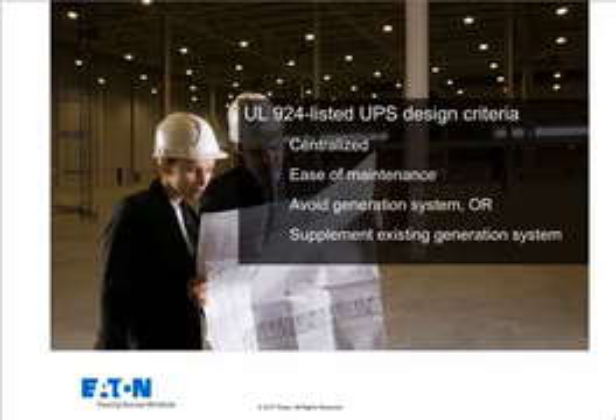Okay, so if I am considering a UPS for this, for a UL 924 application, emergency lighting, the UPS offers a centralized system where you have all of your maintenance done in one place. For example, monthly maintenance, instead of being done on several hundred wall-mounted devices, can be done in one UPS. And by monthly maintenance, we're talking about coming up to the UPS and removing utility power and verifying that the lights stay on and the UPS does in fact run on its batteries, and then returning utility power and verifying that the battery charger does start and begin to charge the battery. So that's one test, takes place in just a few minutes on one device.